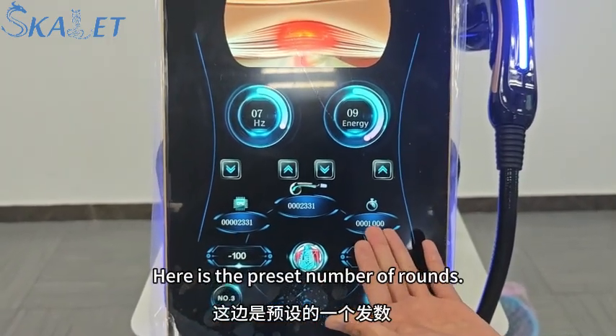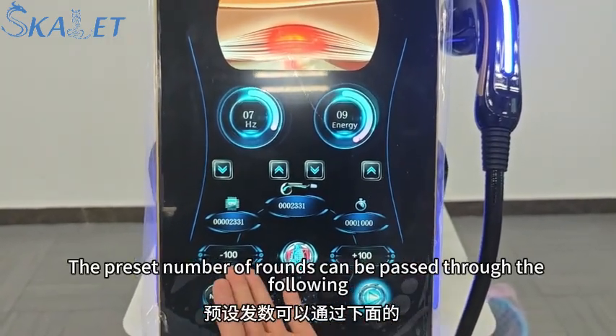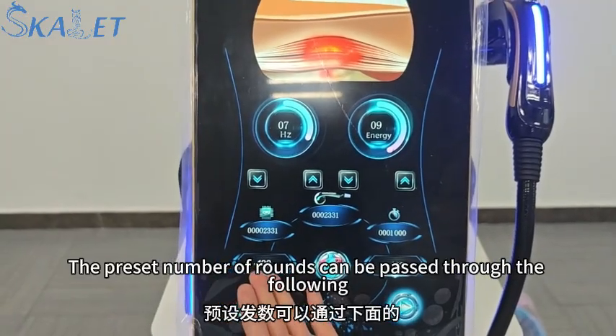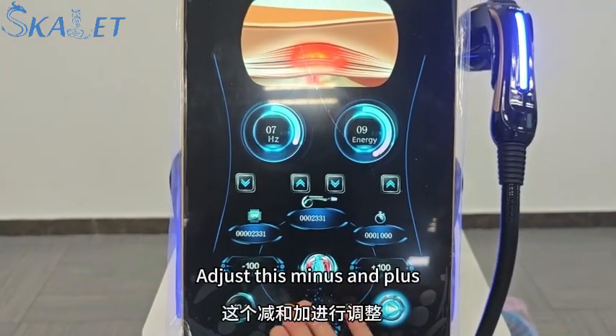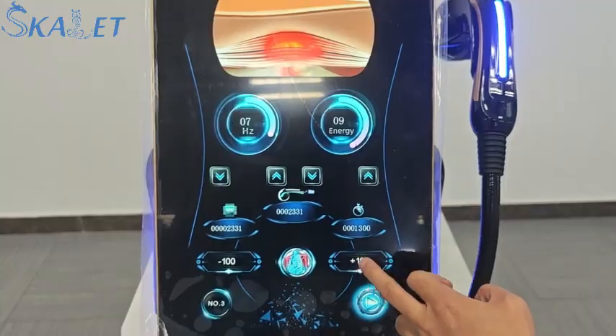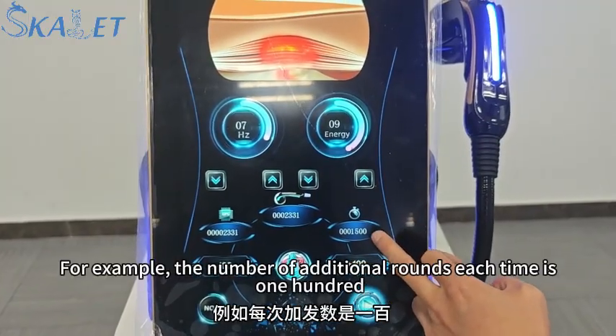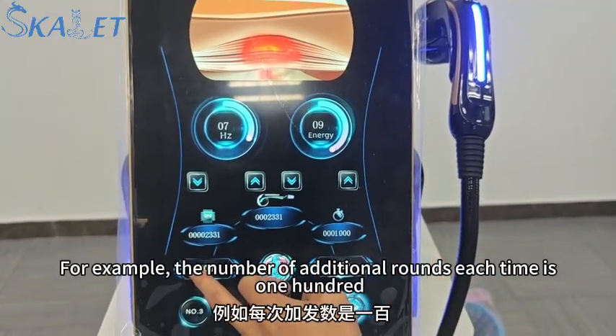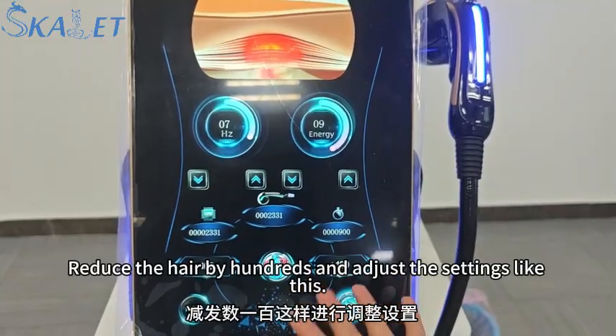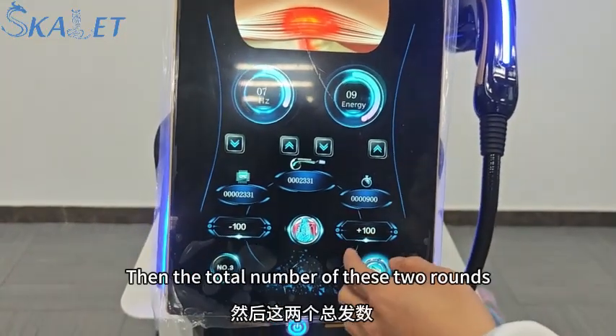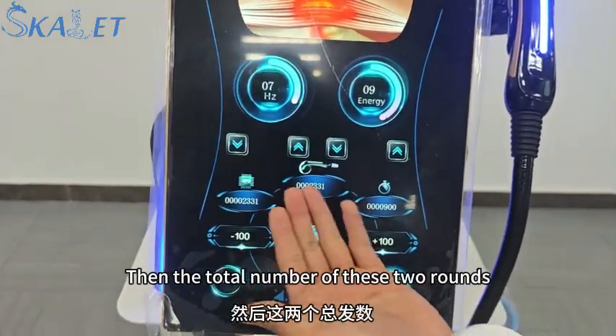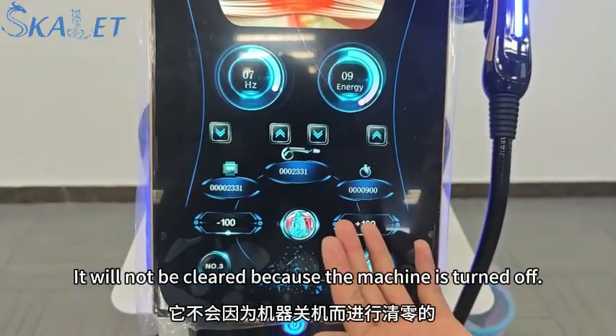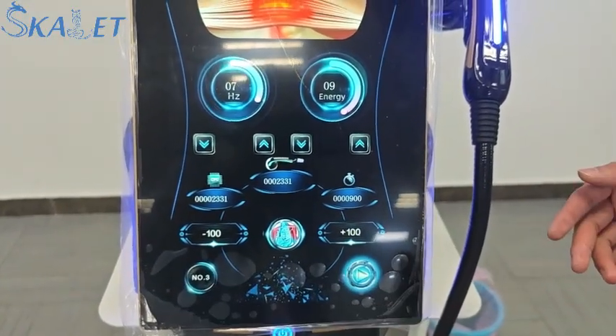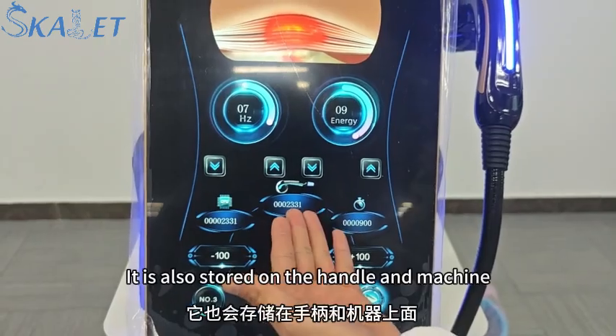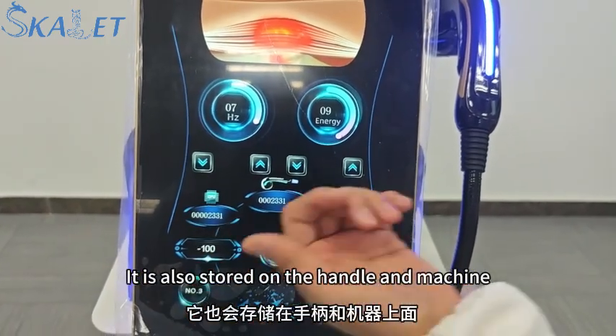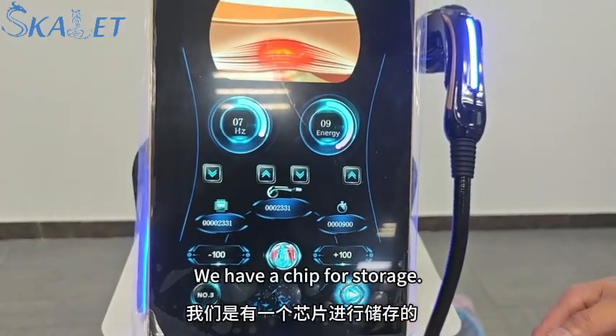Here is the preset number of runs. The preset number of runs can be adjusted through this minus and plus. For example, the number of runs added each time is 100. Reduce it by hundreds and adjust the settings like this. Then the total number of these two runs will not be cleared because the machine is turned off. Even if we shut down, it is also stored on the handle and machine. We have a chip for storage.